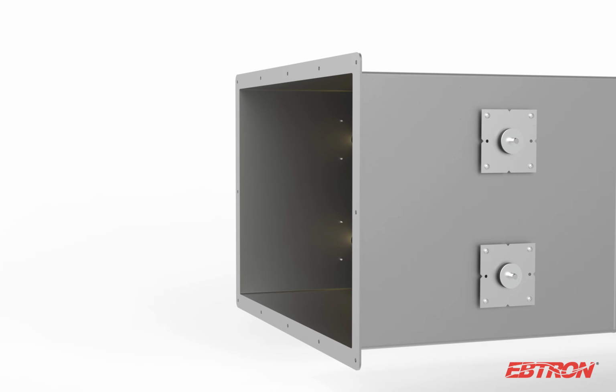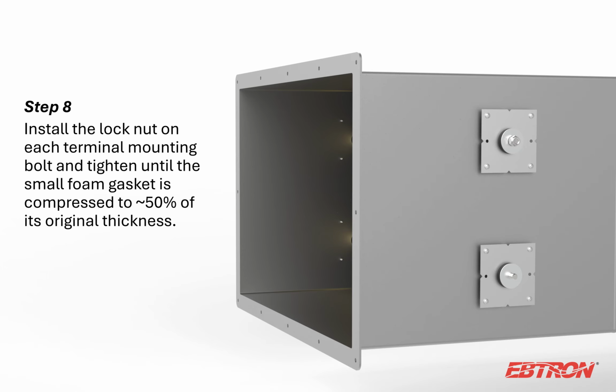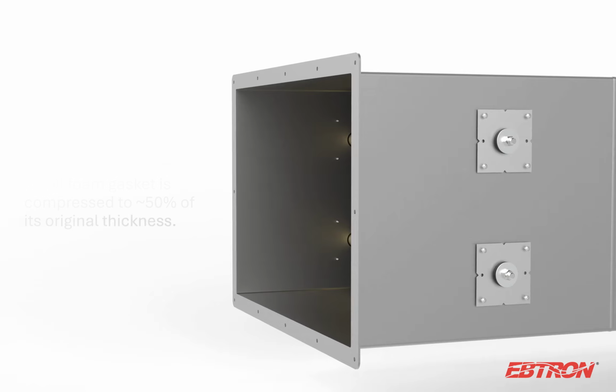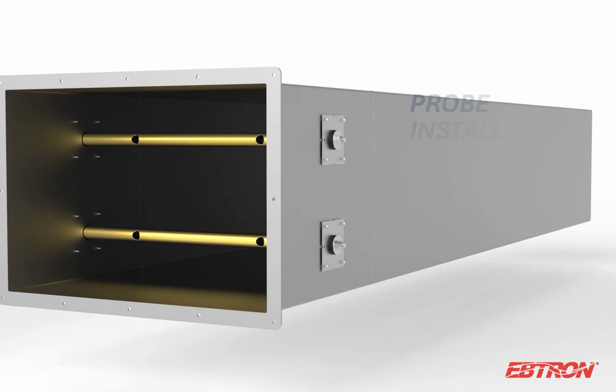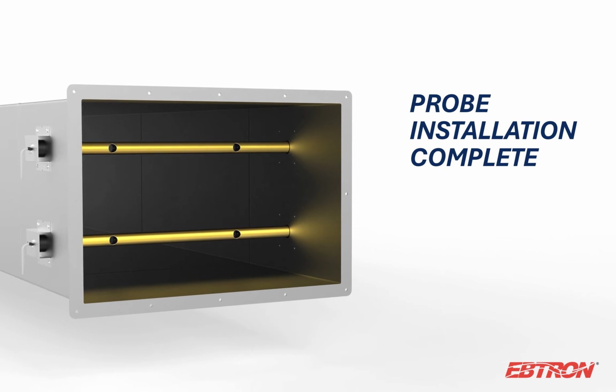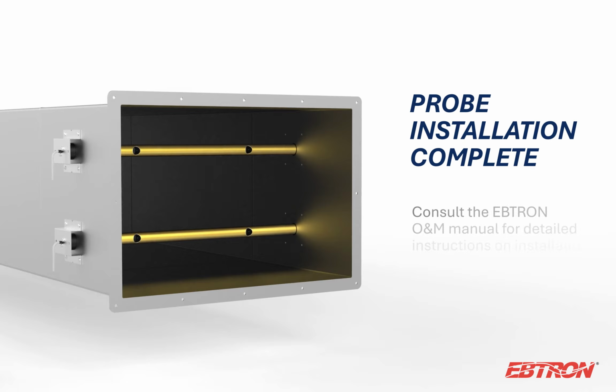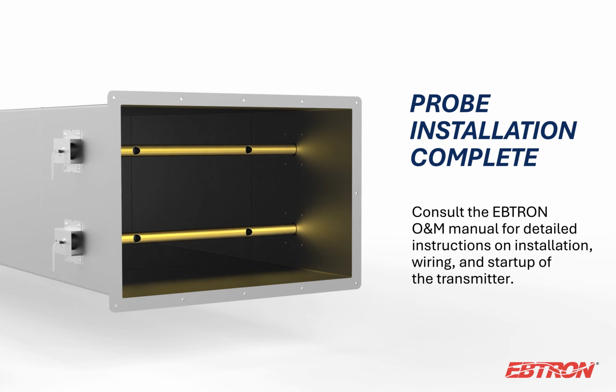Each probe is fully secured by installing the lock nut on each terminal mounting bolt and tightening until the small foam gasket is compressed to approximately 50% of its original thickness. That's it! Probe installation is now complete. Detailed instructions for installation, wiring, and startup of the transmitter can be found in the O&M manual.